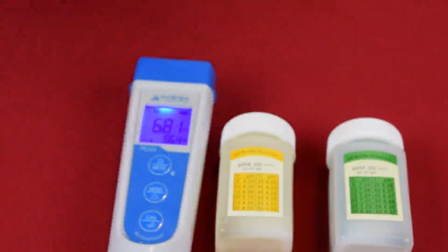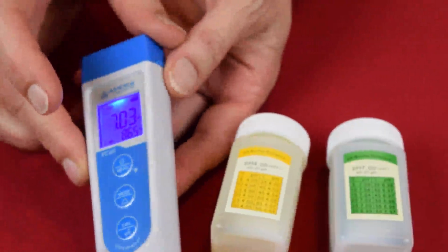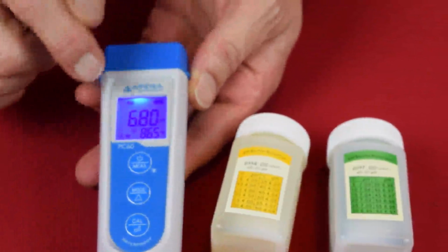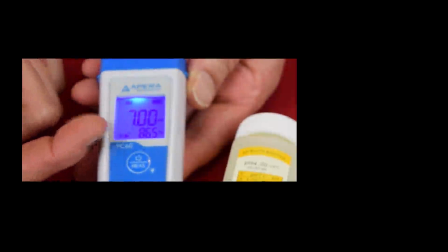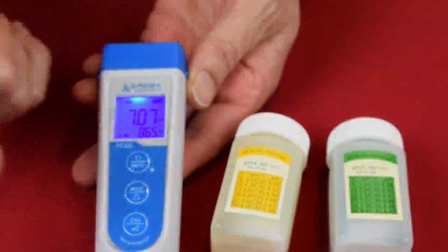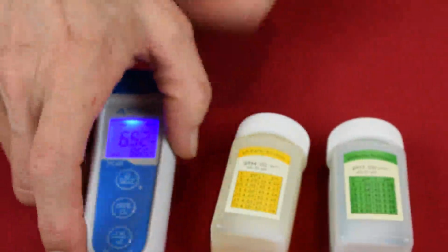Alright, so here's my pH mode. I don't know if you can see that, but there's a little box here, and it's a dark box with light letters pH. And down below you can see an M and an L. I calibrated it. The M was for the 7 pH solution, and then L was for the 4. And to calibrate these, what you do is you pour these solutions in the little bottle, about half of it, and you can use this around 10 times, this bottle here.